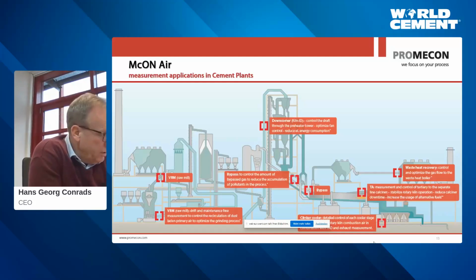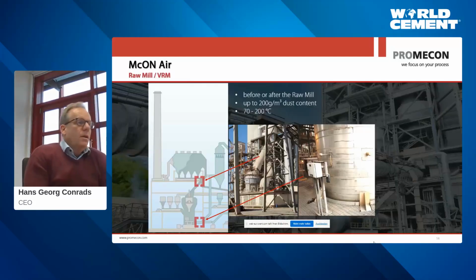So, yeah, we want to discuss how can you save money with this measurement. I've taken out a few examples that we can go through. The first one is quite common application, raw mill. Raw mill, a huge energy drain in your plant, huge consumer of electricity, but like all milling plants, the grinding power and the grinding of the material is only a small portion of the total electricity consumption. One very large factor in electricity consumption is just fan power. So moving the dusty gases around is at least as electricity consuming as grinding them. So fan power is a critical thing.